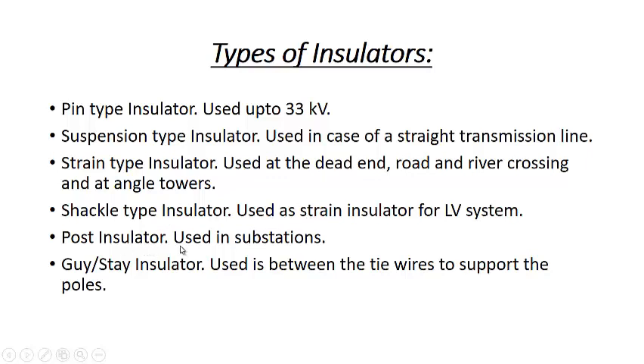Post insulator is a type of pin type insulator which is used in substations. So it is actually a modular design of pin type insulator where the high voltage post insulator can be made by putting one post insulator on another post insulator. In pin type insulator, such configuration is not available, but in post insulator it is available, where we can use more than one post insulator in the higher voltage level.